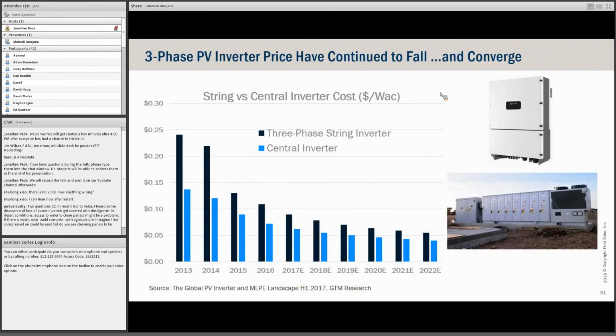Recently, there's been development of string inverters. In the past, we would have hardly considered string inverters viable for large utility scale PV plants, especially looking at this chart, which shows on the y-axis the cost per watt AC of string inverters in black, and in blue the central inverter. The central inverter costs were always lower, but recently companies like Huawei and others have increased the volume of string inverters and managed to bring down the cost by manufacturing scale.